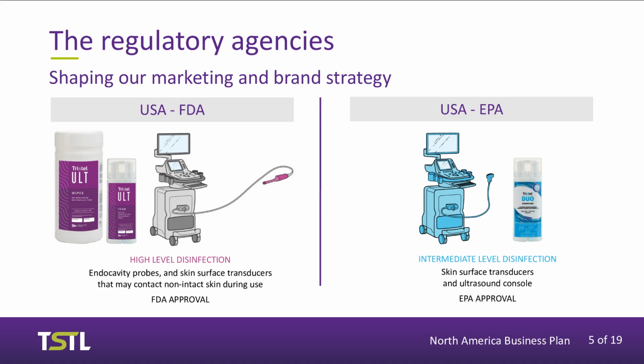On the left-hand side, you can see that the part of the probe that goes inside the body, that's the part that requires high-level disinfection and is colored in pink. On the right-hand side, that's a skin surface transducer that is attached to the console by a cord. Well, all the skin surface transducer, because of its Spalding classification, and all of the rest of the console and the cord require intermediate or low-level disinfection. We've colored them in blue to signify where our Duo product is to be used. And if you piece the two pictures together, you can see that our two products can do every part of an ultrasound system for whatever use that may be put to in the United States with appropriate regulatory authorization.